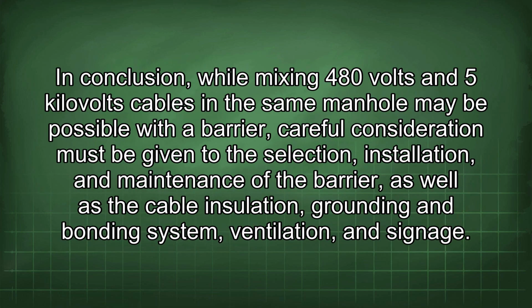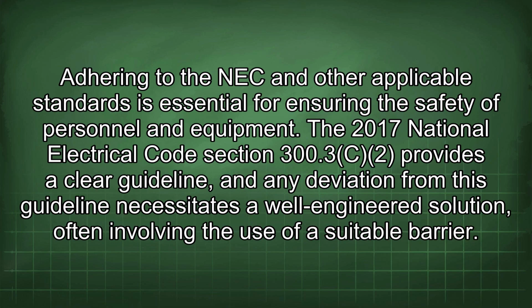In conclusion, while mixing 480 volts and 5 kilovolts cables in the same manhole may be possible with a barrier, careful consideration must be given to the selection, installation, and maintenance of the barrier, as well as the cable insulation, grounding and bonding system, ventilation, and signage. Adhering to the NEC and other applicable standards is essential for ensuring the safety of personnel and equipment. The 2017 National Electrical Code Section 300.3(C)(2) provides a clear guideline, and any deviation from this guideline necessitates a well-engineered solution, often involving the use of a suitable barrier.